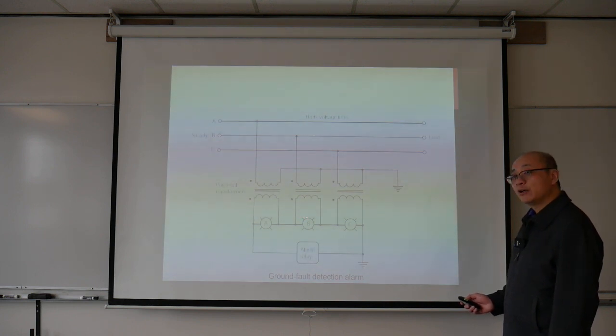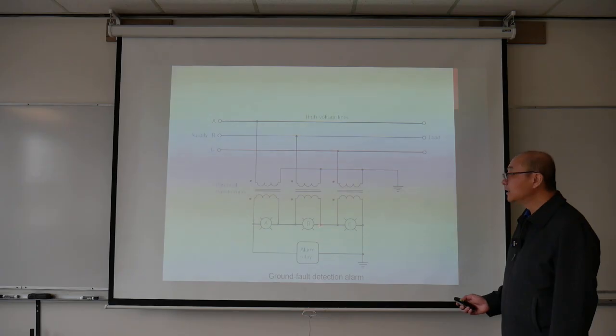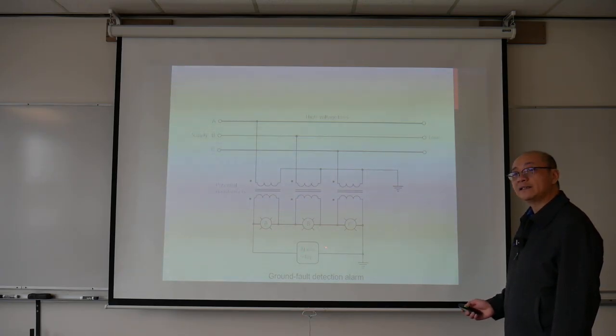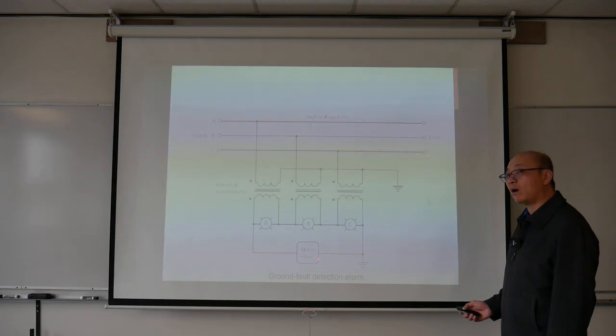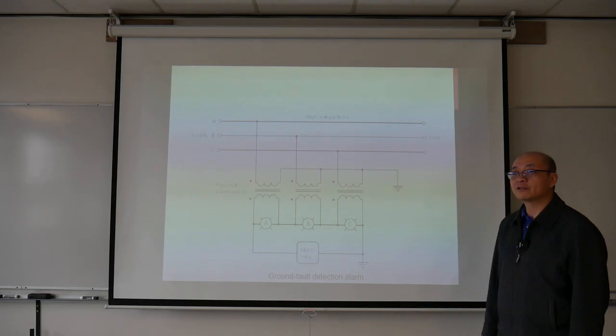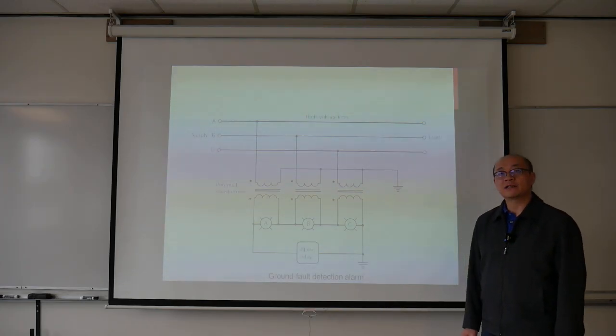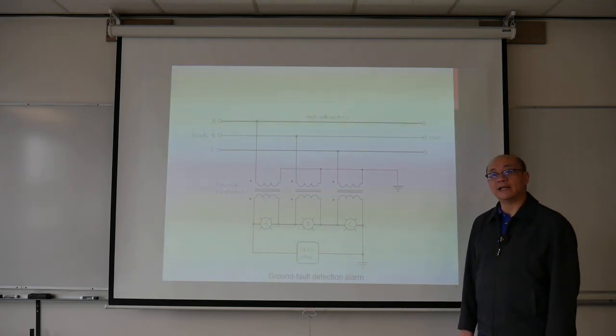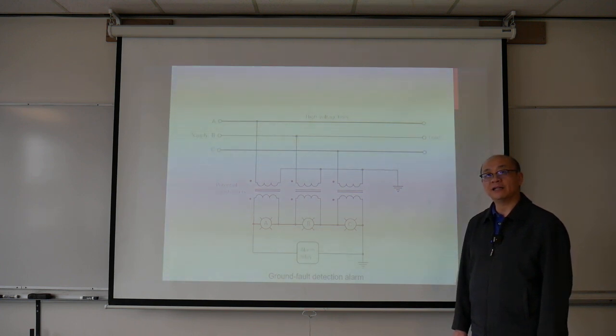Now the secondary side becomes open delta connected. When it is open delta connected, the alarm relay sees the secondary line voltage. Once the alarm relay sees the secondary line voltage, it sends the alarm signal to sound, indicating there's a ground fault happening in the circuit. So here are a few slides showing you the instrument transformers used in three-phase circuits. If you have any questions, you can send us an email or connect with us online.